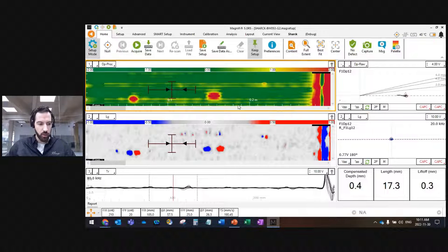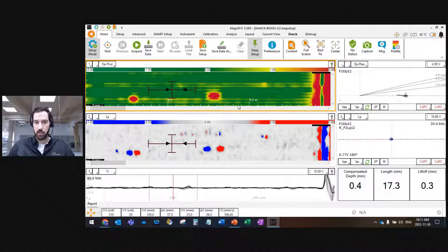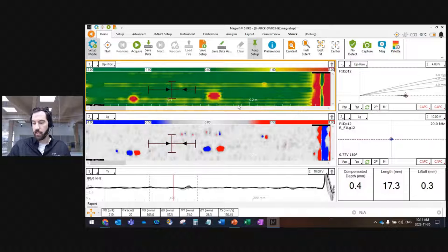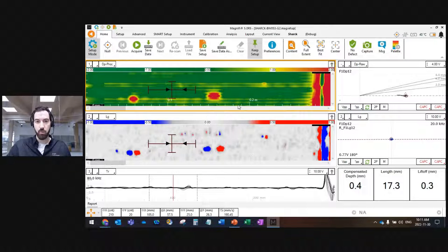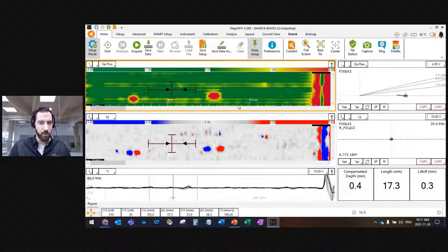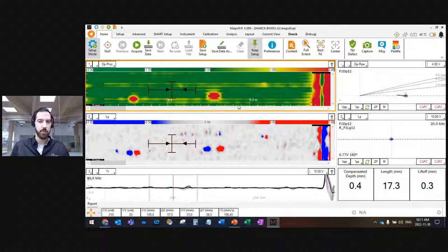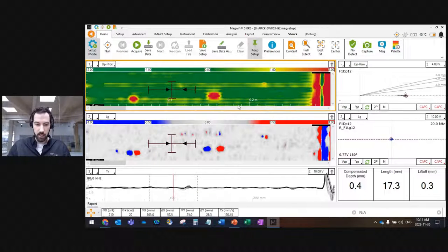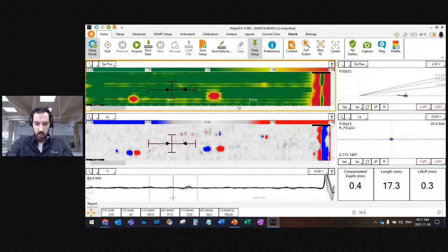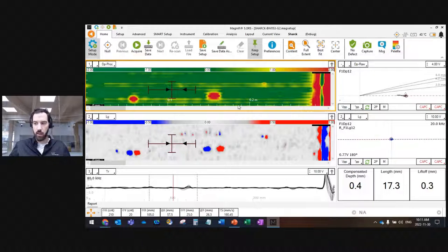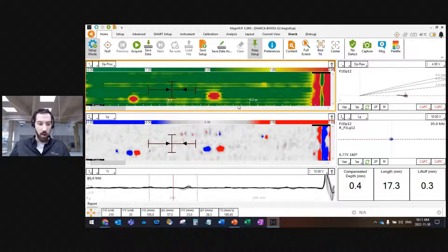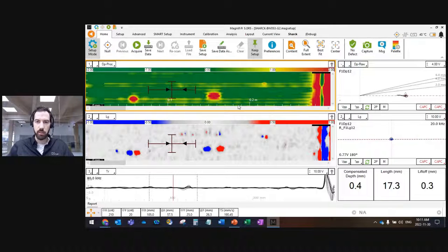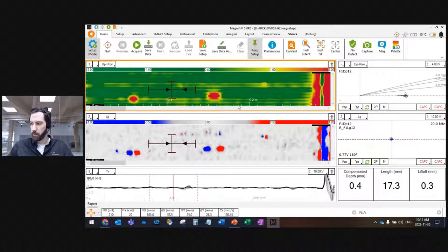What I need to do here, I need to compensate my signal, compensate my data for this magnetic property of the carbon steel. This is one very crucial step that a lot of eddy current systems are not doing. They're just providing this data as you see it on the screen without compensating for liftoff, compensating for all these things that will affect the depth.